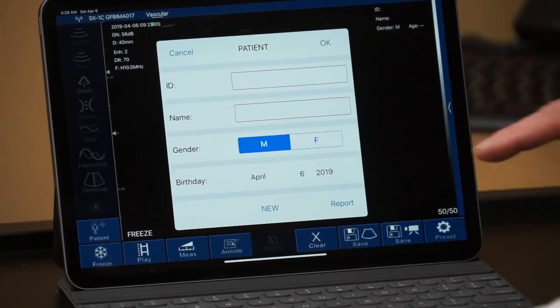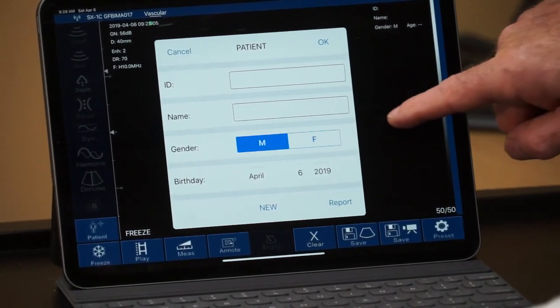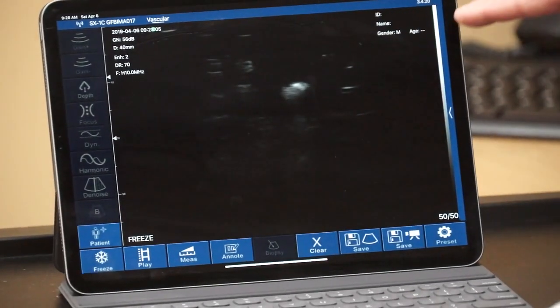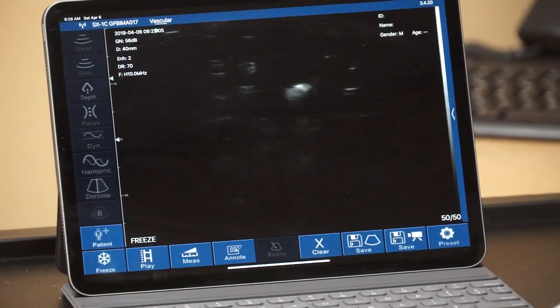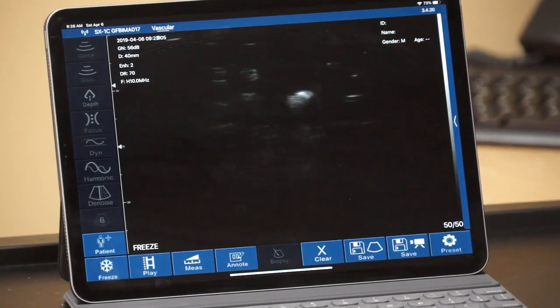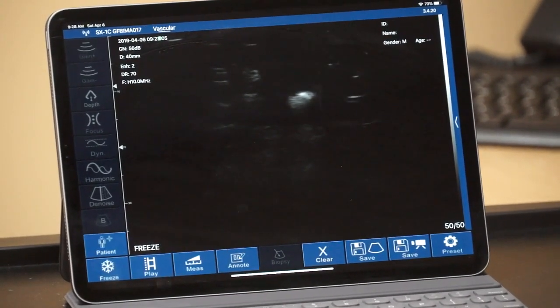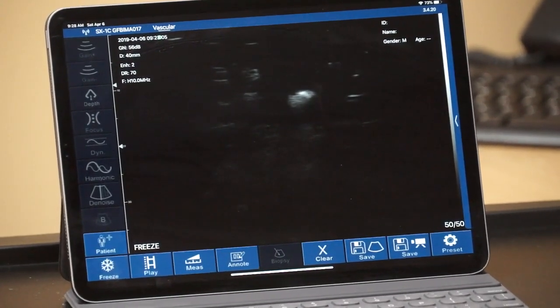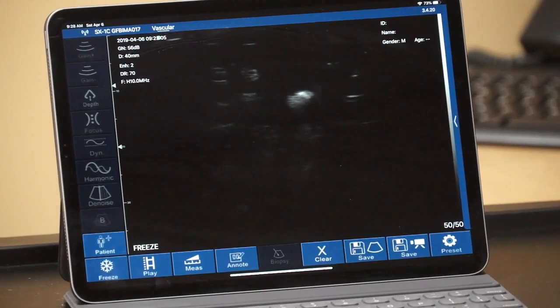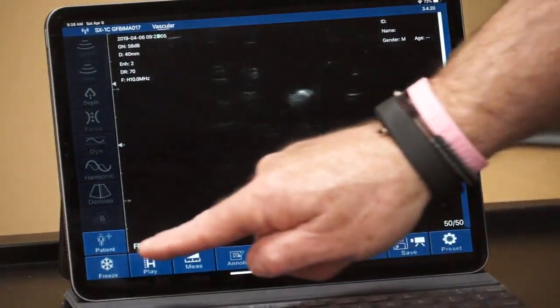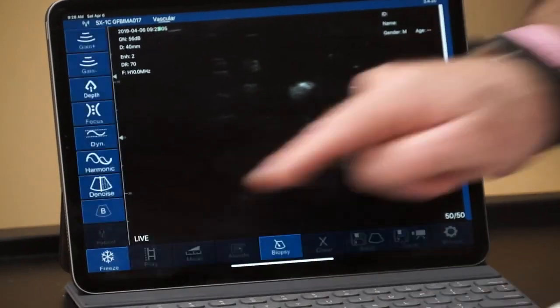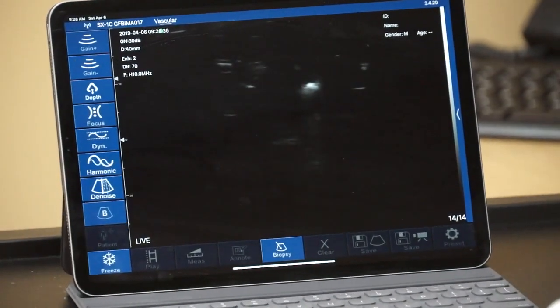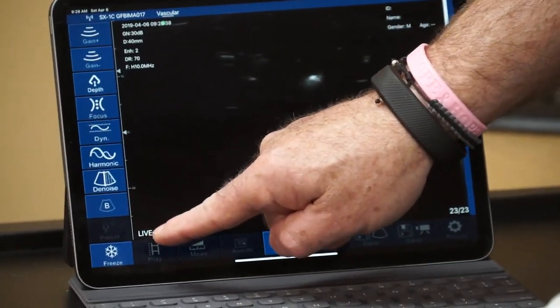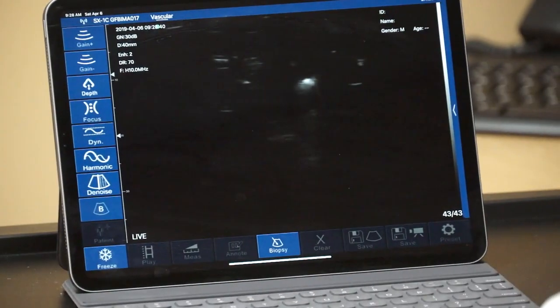Once the demographics are entered, touching anywhere on the screen will leave that, and up here in the upper right-hand corner, all of the patient information will be displayed: the patient ID, name, gender, and age. At that point, we're ready to begin scanning. One of two ways activates the probe out of the freeze mode. Either touching the freeze button here in the lower left corner of the screen, and now we can see the word live in the viewing screen indicating we're ready to begin scanning.